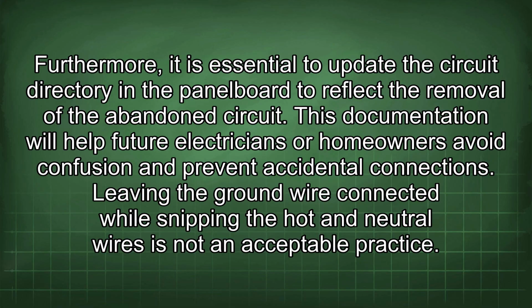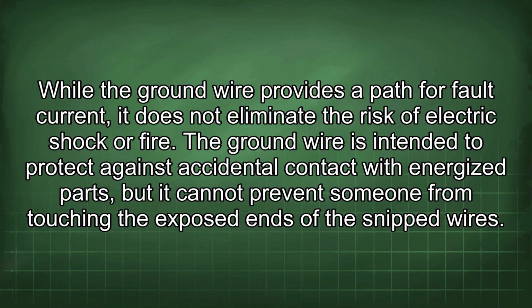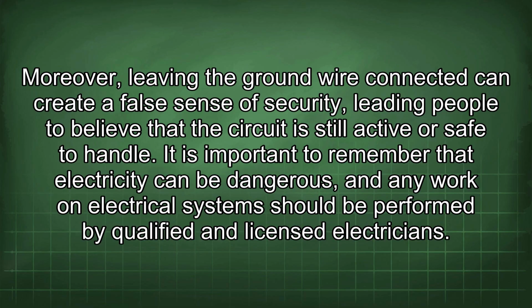Leaving the ground wire connected while snipping the hot and neutral wires is not an acceptable practice. While the ground wire provides a path for fault current, it does not eliminate the risk of electric shock or fire. The ground wire is intended to protect against accidental contact with energized parts, but it cannot prevent someone from touching the exposed ends of the snipped wires. Moreover, leaving the ground wire connected can create a false sense of security, leading people to believe that the circuit is still active or safe to handle.